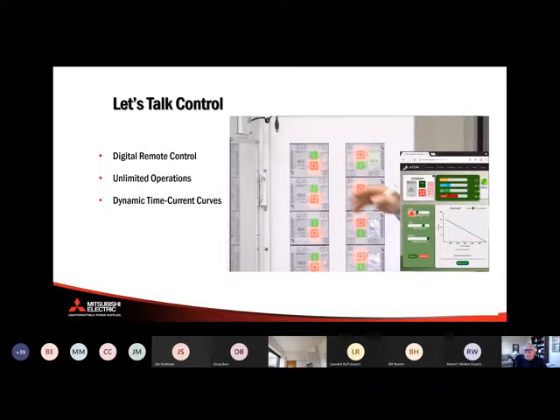You can go into the software inside this panel and see all of the different circuit switches. Suppose this 40 amp becomes too small and you need an 80 amp. You just go in and change it digitally in the software from 40 amps. You see the 40 over here, and you just slide the radio button to the right until you get to 80.